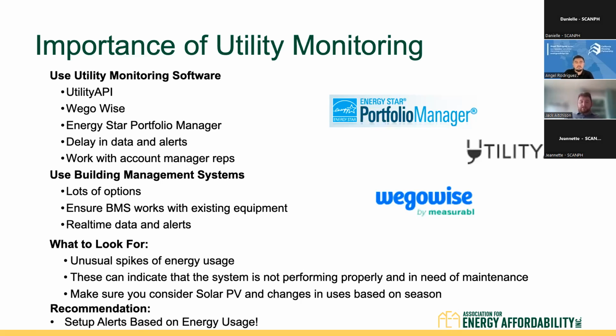So you may want to consider using a building management system. There are lots of options for building management systems. One thing you need to make sure of when selecting one is that it works with the existing equipment. Sometimes central heat pump water heaters have a port that only works with certain building management systems. So you need to make sure that your system is working properly.